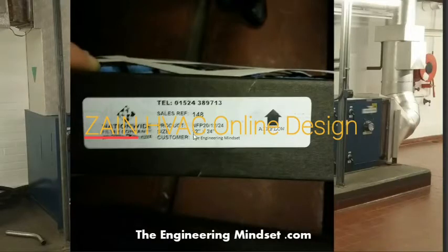You'll also find some information on the side of most of the panels, so you can see the size there. You've got the product description and the company who makes it, and the size of the filter there. This one's in inches, and who the customer is. I've just edited that quickly. But more importantly, you've got the direction of airflow, so you know how to install that within the AHU, how to slide that in so that the air will be passing through this way and out off into the supply duct. It's important to get that round the right way.